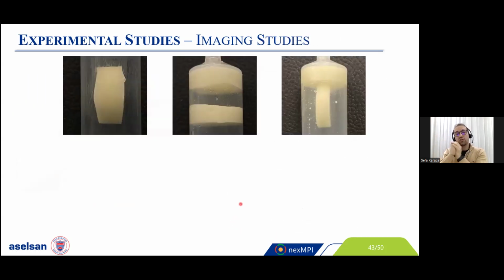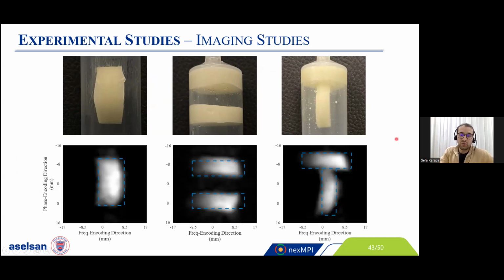We continue with our experiments by designing this MRI phantom. This is basically a mixture of oil, gelatin, and water, and we are just trying to capture the shapes of these three phantoms. These are our low field MRI results for our experimental studies. As you can see, we can capture the shape of each phantom quite clearly, but we still have a geometric distortion artifact, especially in the peripheral region of our field of view. This is because of the field inhomogeneity value.